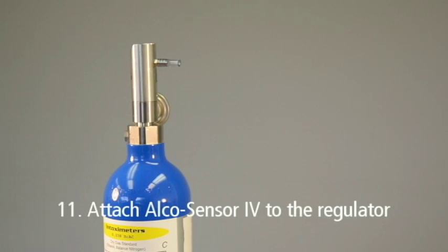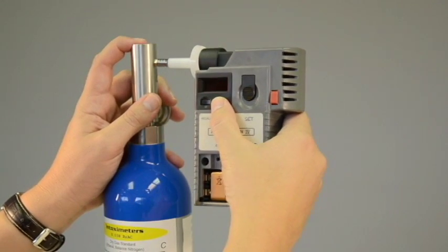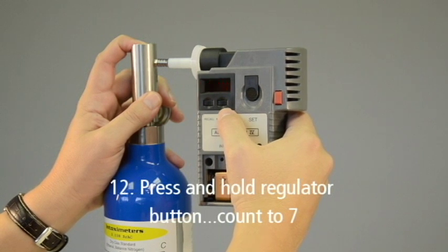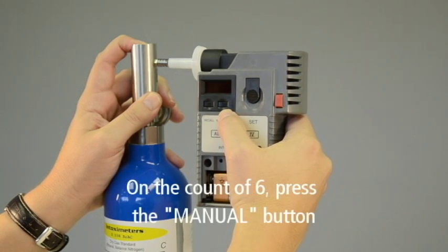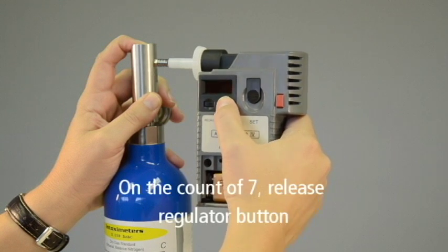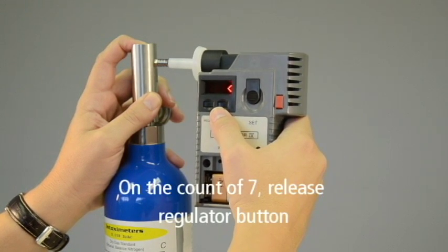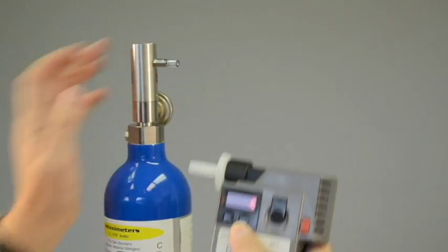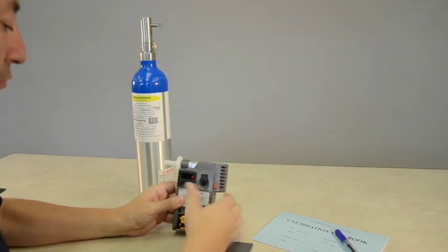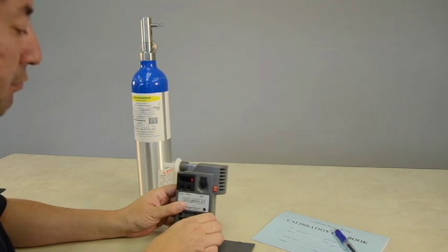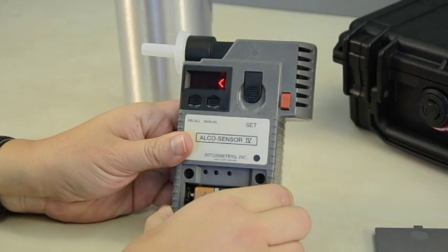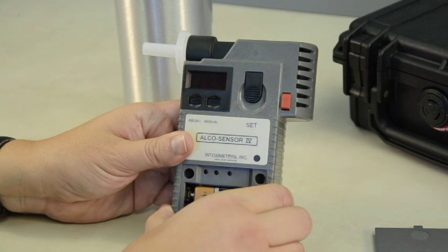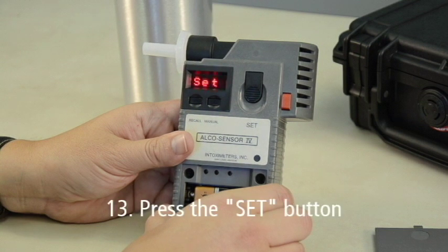Now attach the AlcoSensor IV and mouthpiece to the regulator. Next, press and hold the regulator button and count to 7. When you reach the count of 6, press the manual button. On the count of 7, release the regulator button. Gas must be flowing through the mouthpiece when the manual button is pressed. Remove the AlcoSensor IV and mouthpiece from the regulator. The instrument will automatically make the necessary internal calibration adjustments and will display the newly programmed calibration value for a few seconds. When the instrument flashes Set, press the Set button.